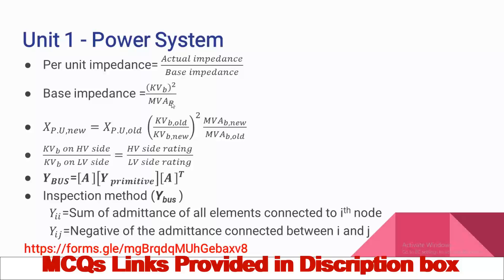These are new values. This calculation is required for the transmission line when the actual impedance value is given. The base impedance of the transmission line can be calculated using this formula. The change of base formula is: X per unit new equals X per unit old multiplied by (kV-base old divided by kV-base new) squared, multiplied by (MVA-base new divided by MVA-base old).